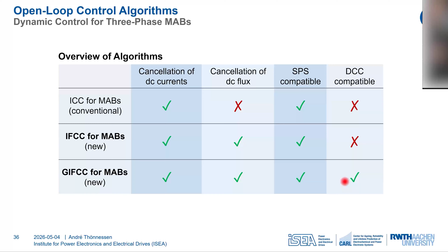By doing so, you can see we have closely no DC bias current here anymore, and also the flux DC component is cancelled. However, during the transition from one waveform to the other, we can see that we exceed the no-load hexagon once. For larger load steps, this can also risk saturation in the transformer core, so we must prevent it.